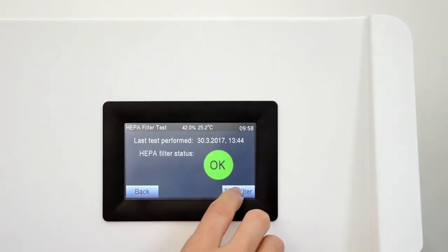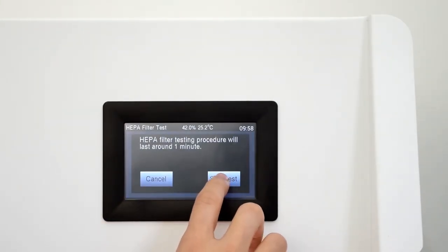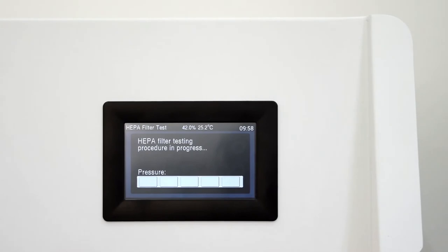The most important function is the HEPA filter test. This test will measure the airflow pressure of the filter and show the result. If the results are good, it means that the filter has no damage and it will maintain the constant airflow inside the working area.